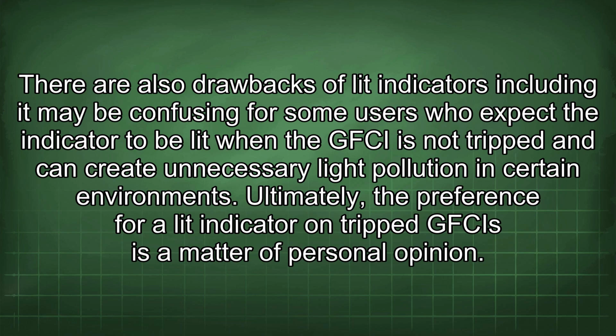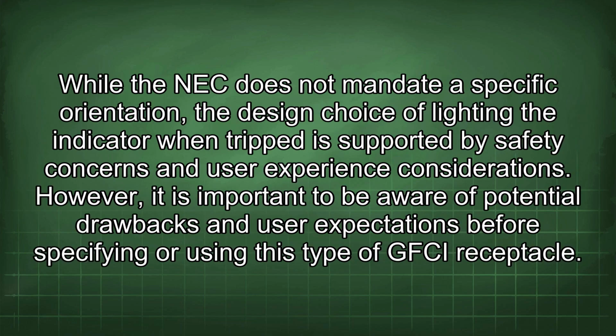Ultimately, the preference for a lit indicator on tripped GFCIs is a matter of personal opinion. While the NEC does not mandate a specific orientation, the design choice of lighting the indicator when tripped is supported by safety concerns and user experience considerations.